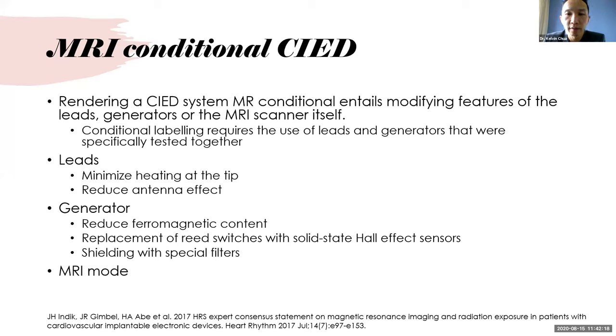The generator, on the other hand, faces maybe more challenges. Manufacturers have to reduce the ferromagnetic content to decrease magnetic attraction and imaging artifacts. There's replacement of reed switches with solid-state Hall effect sensors, which behave more predictably in an MRI environment. Shielding with special filters limits the transfer of certain frequencies and dissipates energy, reducing the risk of potential damage to the circuitry. Certain devices also have an MRI mode, which features pre-scan system integrity checks, asynchronous pacing, non-sensing modes, disabling of tachycardia detection, increasing the output transient during the scan, and restoration of pre-scan program states and values.